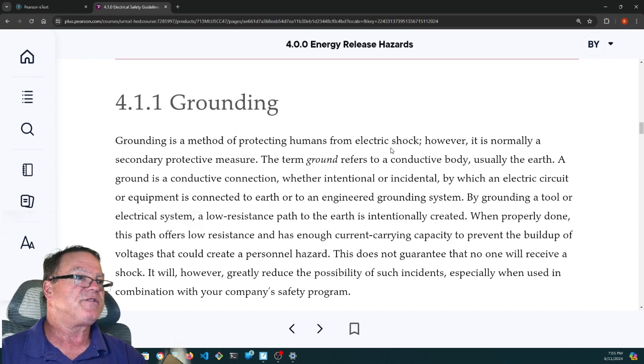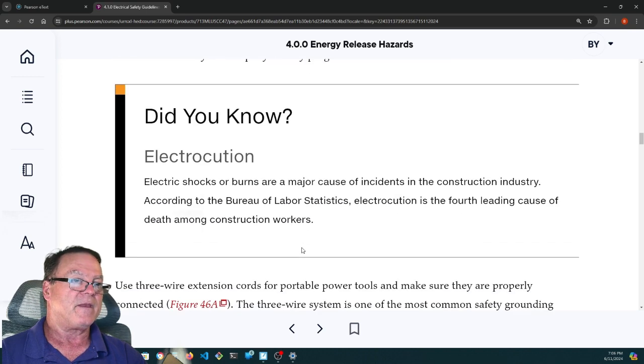Grounding is a method of protecting humans from electrical shock, though it's normally a secondary protective measure. The term ground refers to a conductive body, usually the earth. Ground is a conductive connection, whether intentional or incidental, by which an electric circuit or equipment is connected to earth or to an engineered grounding system. By grounding a tool or electrical system, a low resistance path to earth is intentionally created. When properly done, this path offers low resistance and enough current carrying capacity to prevent the buildup of voltages that could create a personnel hazard.